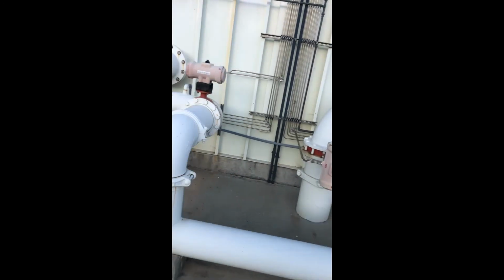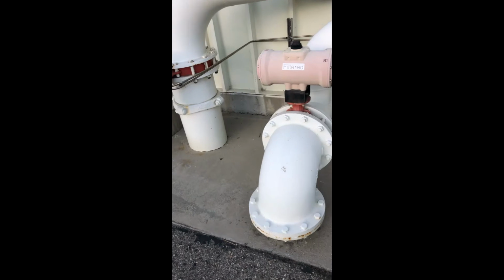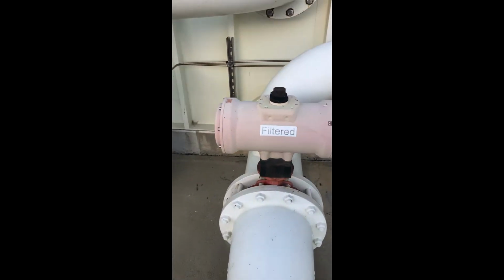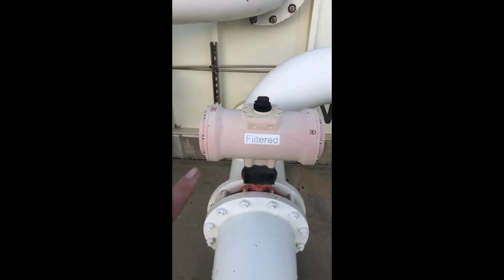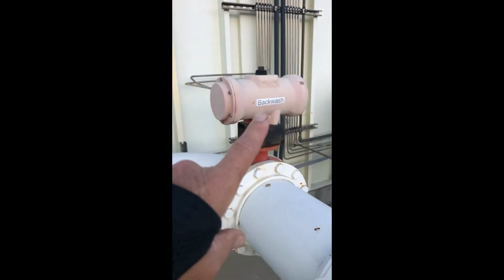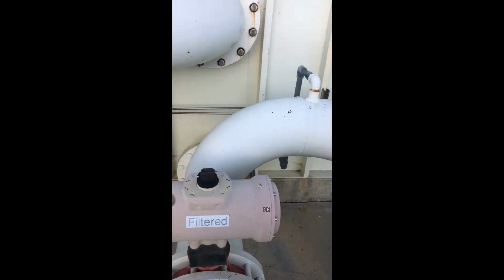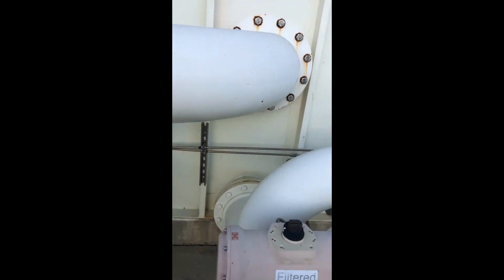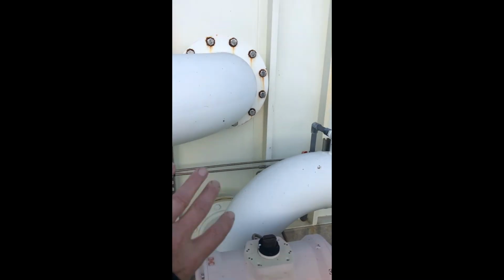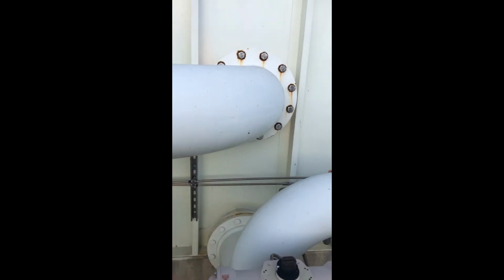So the clean water, when it's filtered, it's open, comes out here. When we backwash, we close this valve, we open the backwash, we send the water the opposite direction into the tank, reverse it through the sand, and then all the dirt gets purged out of the sand and comes out of this pipe here, and that goes to our mud well. The mud well has pumps. We simply push that back to the front end of the plant.